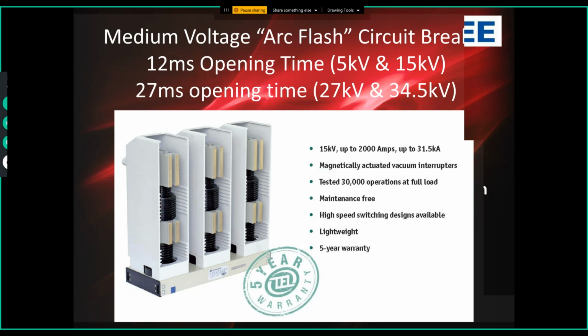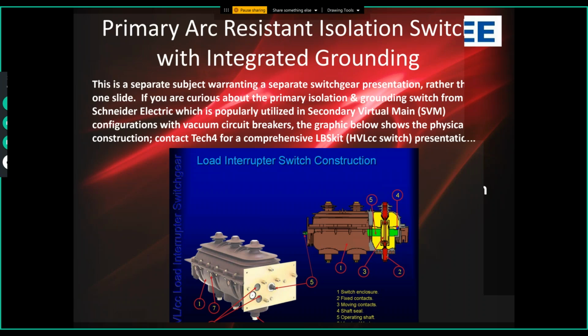But from a safety point of view, if you're going to rack out the breaker, now you've completely isolated and grounded on the load side. So you're grounded to rack, and you're racking the breaker out under de-energized no load conditions as well. So rather than having the line side of the circuit breaker be hot for maintenance of the circuit breaker itself, it's a switch over breaker configuration.